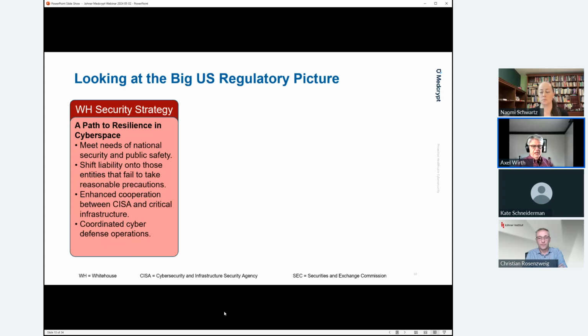Also, the trend is clear here that the liability is being shifted away from the operator of devices to the manufacturer of devices and software. So clearly, it is understood that the earlier in the device lifecycle you implement security, the better the security posture and the lower the total cost of security across the device's operating life will be.